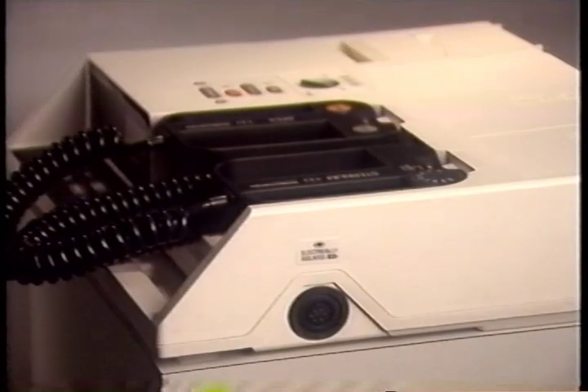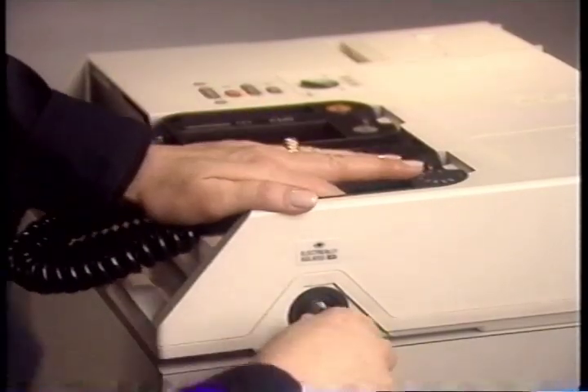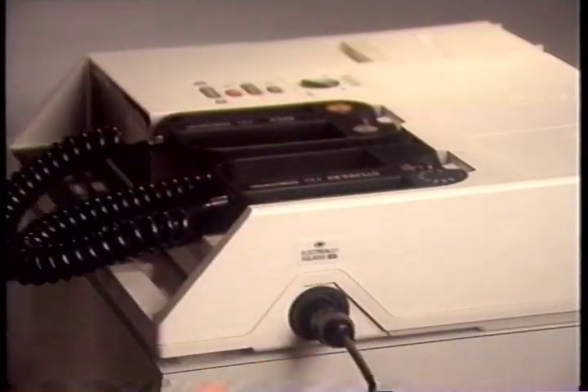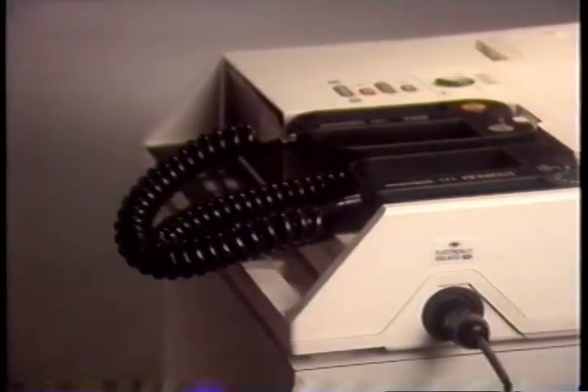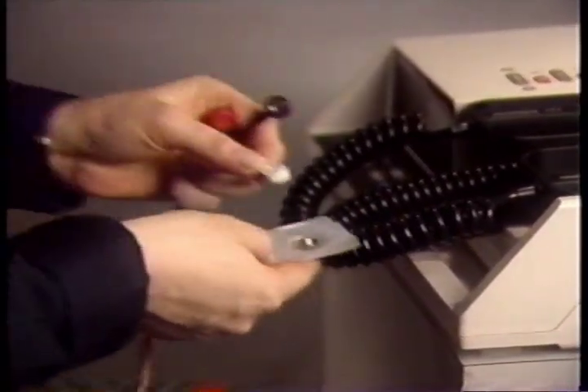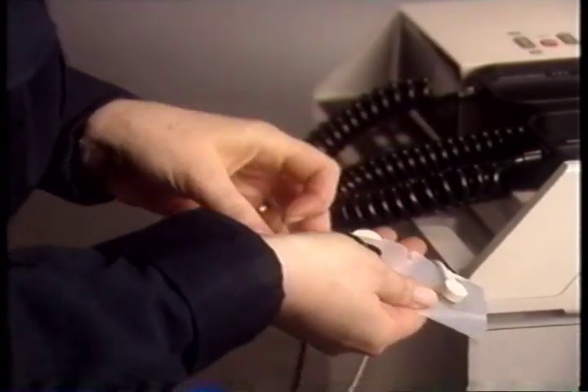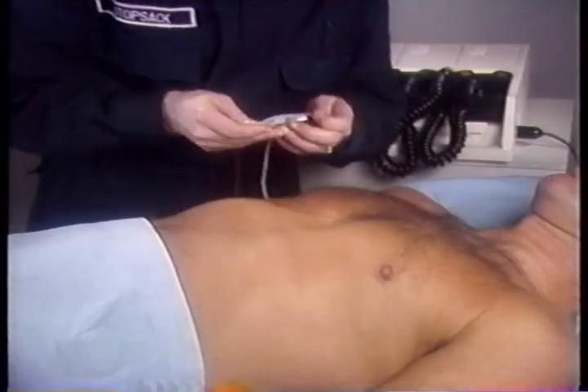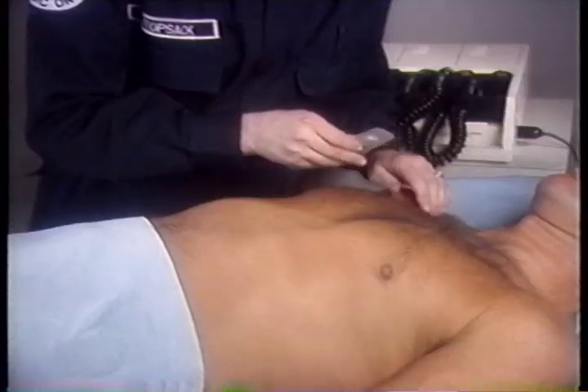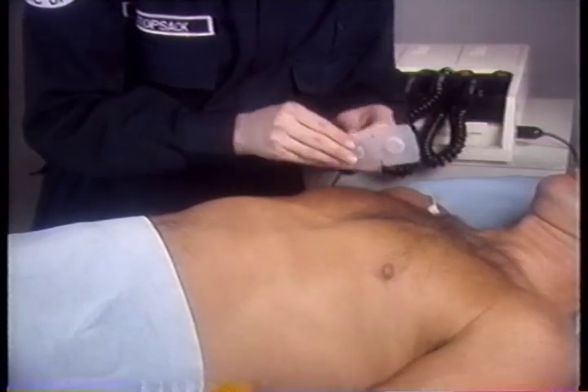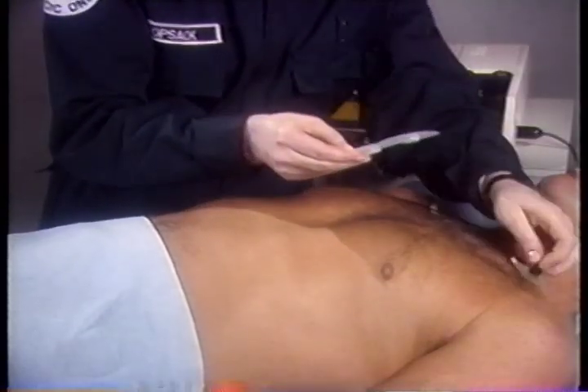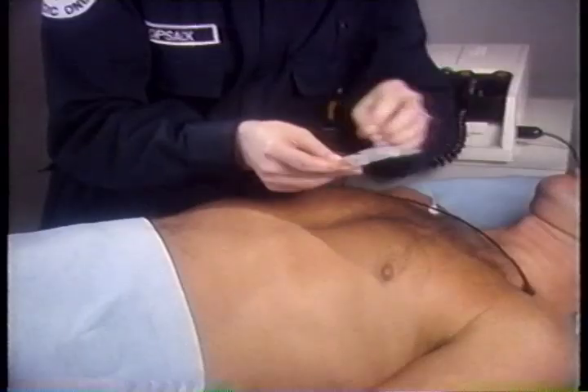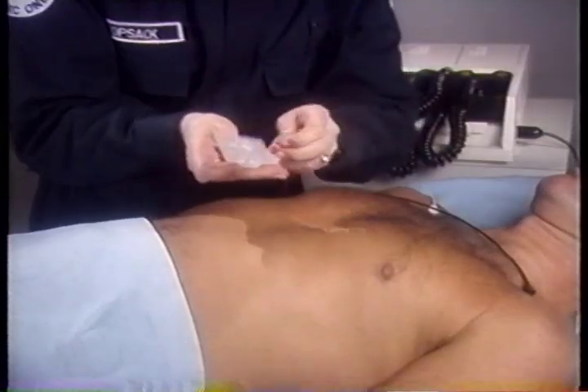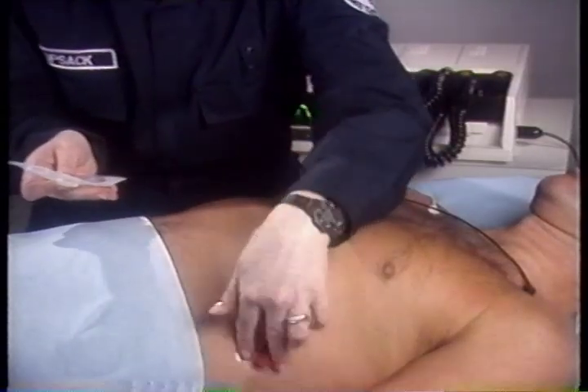To monitor a patient through ECG electrodes, plug the 3-lead patient cable into the cable receptacle on the right side of the device and connect the cable snaps to ECG electrodes. Place the right arm electrode on the patient's upper right chest below the clavicle, the left arm electrode on the upper left chest below the clavicle, and the left leg electrode on the lower left torso.